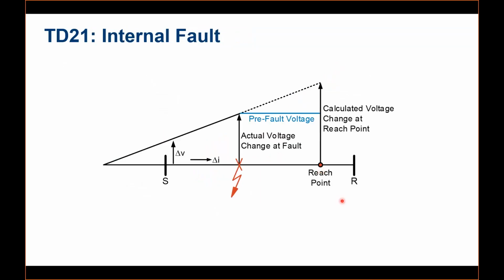All right. Let's consider a fault that is within your reach. This is your reach, and the fault is happening within the reach. If the fault is within the reach, it means it's much closer to your source. So the changes in the voltage and current will be stronger, and the relay will estimate or calculate a voltage change at the reach point. Apparently, that calculation will be higher than the pre-fault voltage that the relay is watching before the fault. In this scenario, the relay will decide it is an internal fault, or in-zone fault.